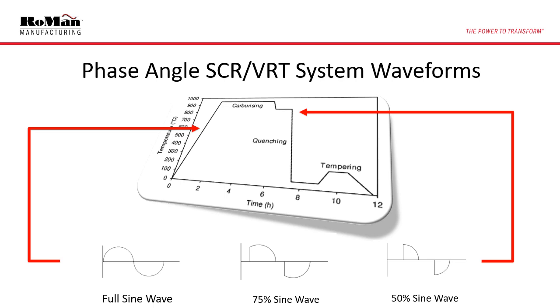Let's look at a typical program for a furnace. As a furnace is in a ramp phase, the control is providing 100% power. And with a VRT or SCR control, this means full sine wave. However, the time a furnace spends in ramp phase is relatively short. The soak phase is a period of time where the furnace is simply maintaining a temperature. During this phase, the voltage is scaled back anywhere between 30 and 60% of full sine wave. You can see on these waveforms that there is a considerable amount of off time. This off time introduces inefficiencies into the system, and inefficiencies cost money.